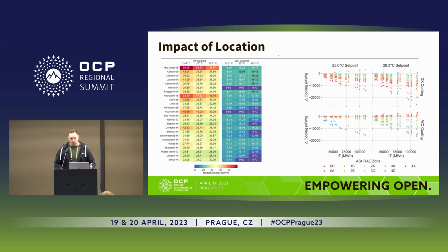And that runs to almost all the 2A and 2B regions. So most of the places where we're about to start developing, the majority of our data centers do not respond well, from an energy and carbon point of view, to raising temperature in a water-cooled system. What's worth noticing here is that water-cooled systems are always more effective than direct air, regardless of where you are in the world. It's a better system, but there is a capital investment in that.